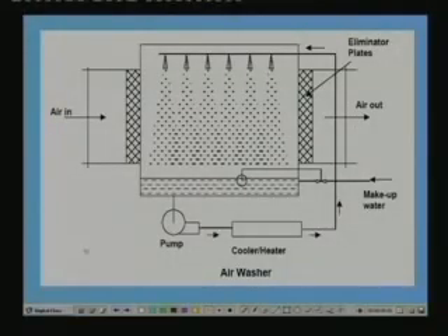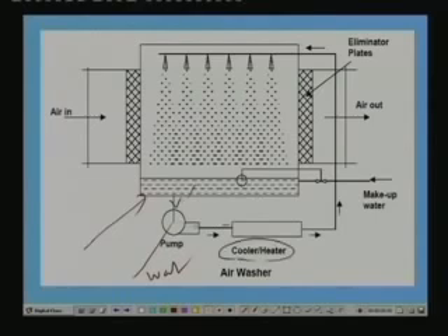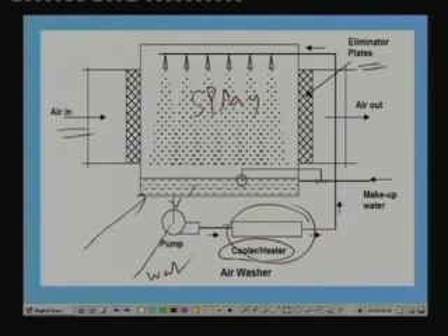So, this is the air washer, we have a water sump, this is the water. This is connected to a pump, a cooler or a heater. So, water is taken from the sump, it is either cooled or heated, and it is again sent back to the air washer, that means it is sprayed. The same water is sprayed after conditioning it. The air enters this air washer through these drift eliminators; of course, you do not require a drift eliminator here, you require it at the exit.